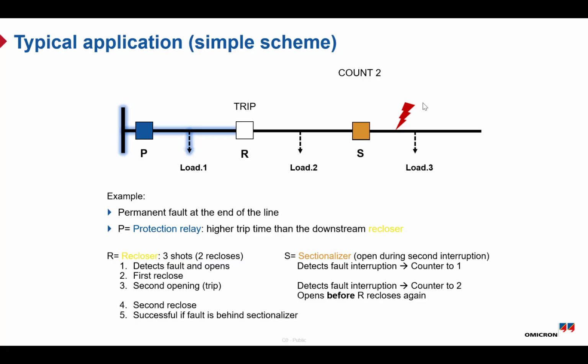Once the count reaches its set value, for example 2 operations in our example, the sectionalizer will open. This happens during the open or dead time of the last reclose shot of the recloser. After that, when the recloser closes again, the faulted section is already isolated and the rest of the line remains energized. So in this case, only a small part of the network is affected and most customers continue to have power.